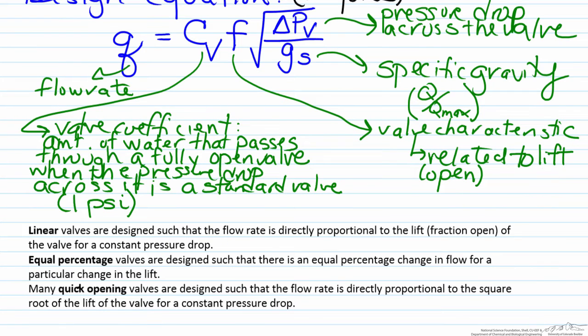For linear valves they're designed such that the flow rate is directly proportional to the lift, in other words how open it is, for a constant pressure drop. Therefore as you double the openness of the valve, you go from forty percent open to eighty percent open, you are doubling the flow rate going through. The valve characteristic F is proportional to L, the lift.